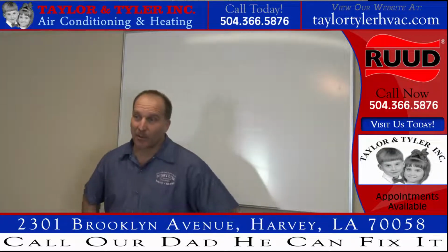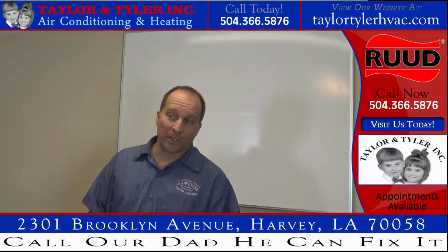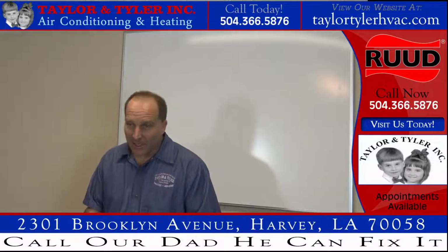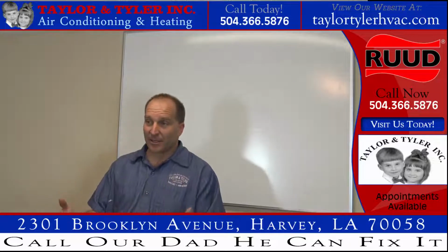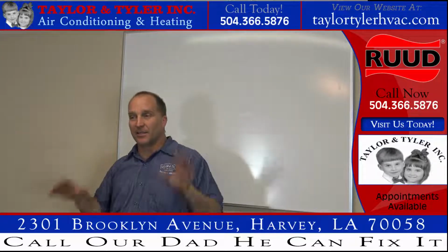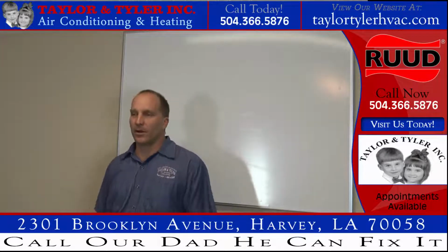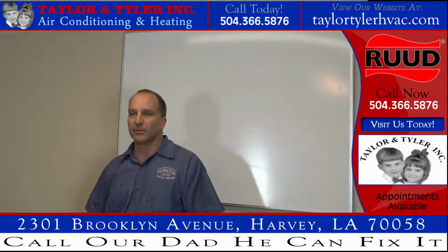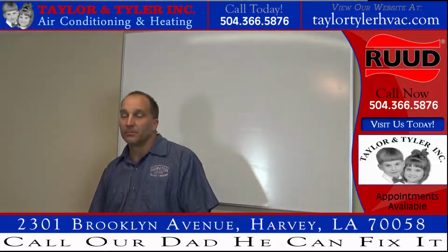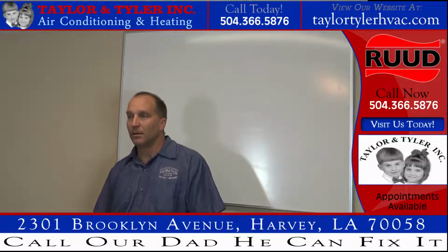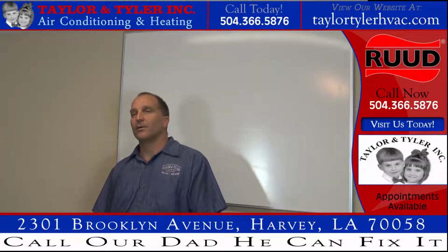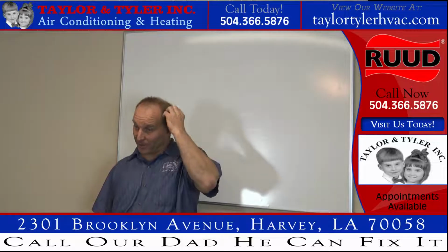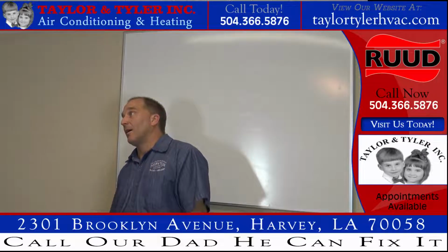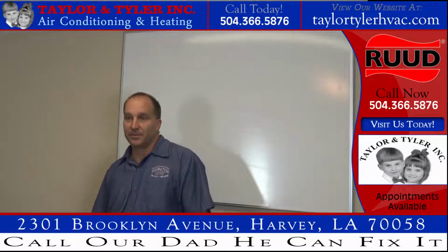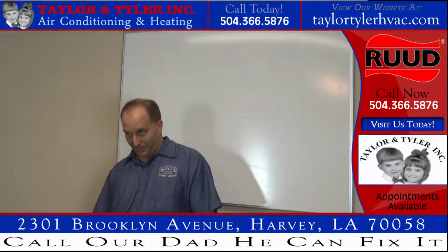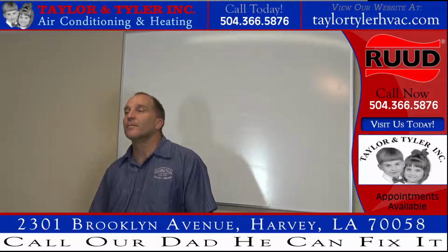I'm going to look inside my return because it's not cooling in the middle of the day, right? So I'm going to stick my light inside the return and I'm actually going to see that I have no return air leaks in this scenario. I have no return air leaks in that vertical air handler. And I have a good delta T. I got to go check my delta T. I got a 14 degree delta T. That's not good enough.